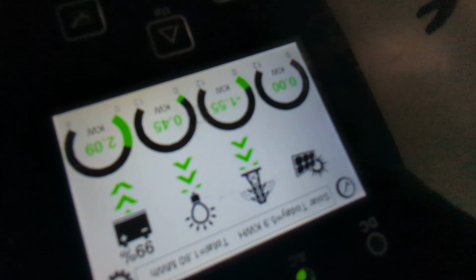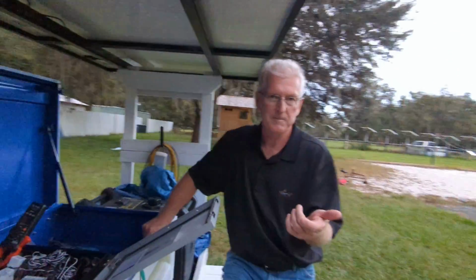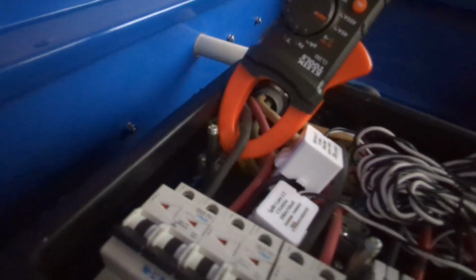So what I'm hoping you're going to see, because of the tests that we did today and the evaluations that we did today, number one, I think you should be better able to balance your loads because you know what is red and you know what is black, right? Okay. Number two is we should not have the grid breaker failures anymore, right? And that was because of a loose connection on the grid breaker.